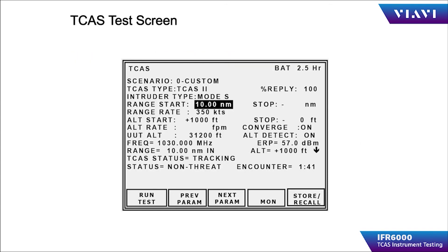The TCAS operation screen is where the operator can configure the physical parameters of the simulated target such as start distance, altitude, altitude rate, and velocity. It also provides the basic measurements of the TCAS being tested such as frequency, power level, and whether the target is being tracked.